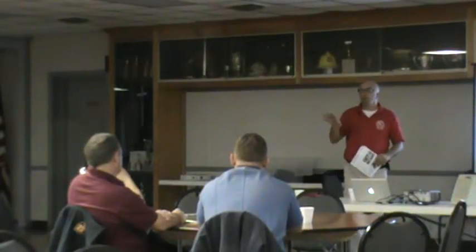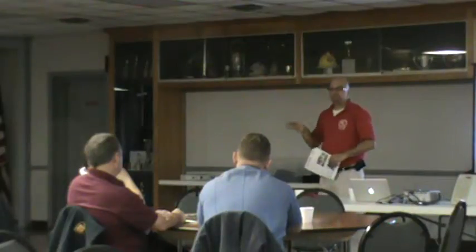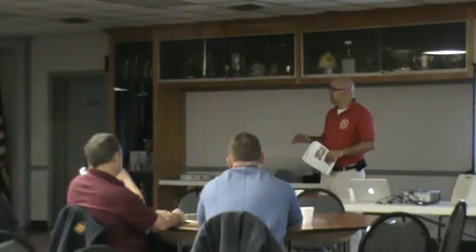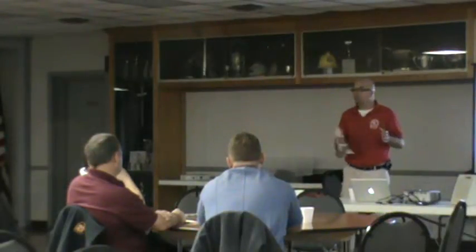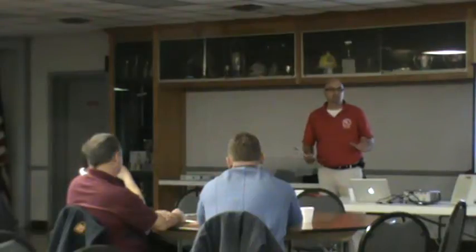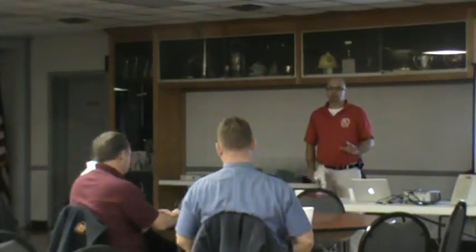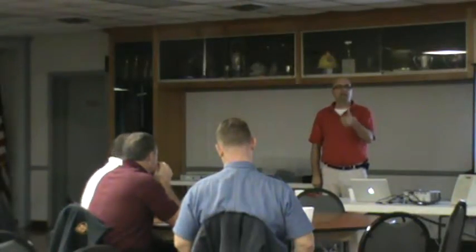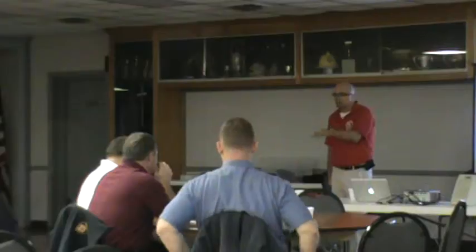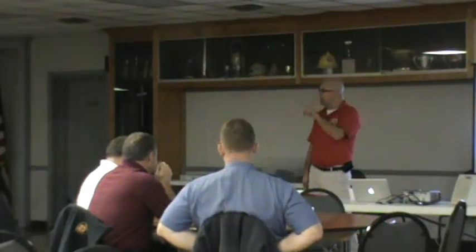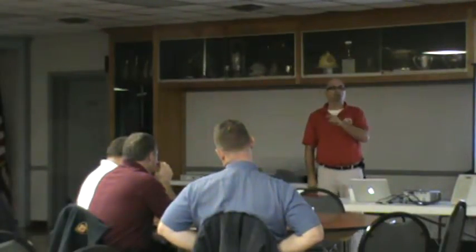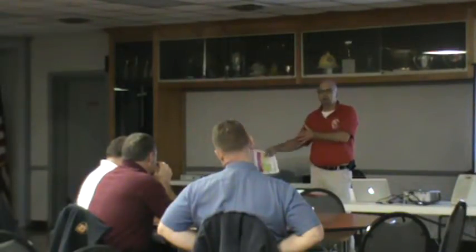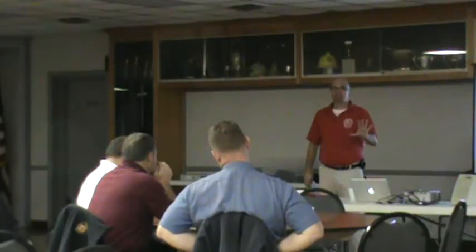A lot of times, ironwork companies can do an emergency Band-Aid on a fire escape and make it functional. You know what I'm saying? So just so you know the options that are out there, you don't have to fully fix a fire escape. You're not going to remove the violations with any of these Band-Aids. This is just to tell you that at every situation, step number one, besides fire watches and vacating the building, there's satisfactory scaffolding out there that has the right rise and run on the stairs and everything that will act as a temporary second means of egress. They do this on buildings all the time when they need to reconstruct the second means of egress inside. They put it outside. They do it all the time. I'm just giving you a suggestion. I'm not telling you this is right.